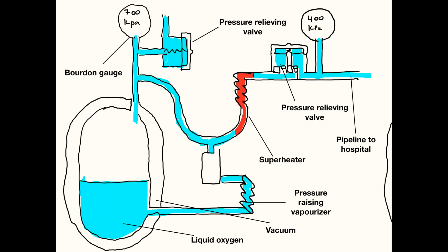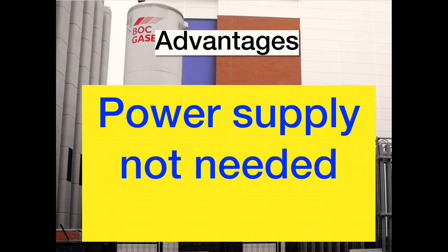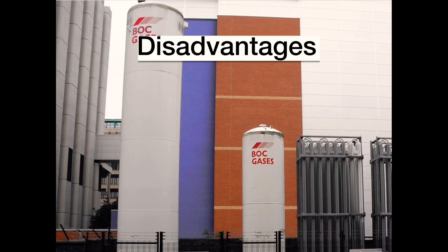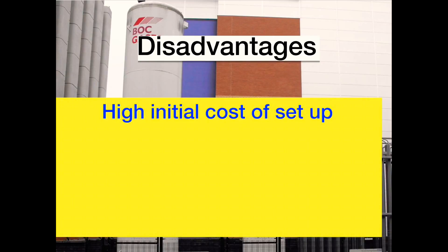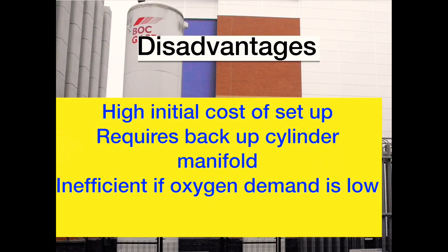The VIE is a very useful mechanism for storing oxygen. It has some advantages: it does not require a source of power, and it is highly efficient in terms of space compared to storing oxygen as a gas. The VIE also has some disadvantages: it has a high initial cost of equipment, it must have a backup cylinder supply, and it might be inefficient if low demand means that significant amounts of oxygen are being vented to the atmosphere. It may also present a fire risk and should be sited appropriately.